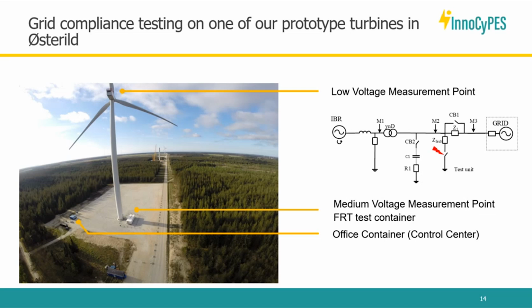We can obtain different topologies of faults by changing these impedances. You can apply two-phase or three-phase faults, and basically, from the point of view of the turbine, it's a fault that the turbine should ride through. This is a very established way of applying faults and validating and certifying turbines for faults, and this is what I'll show in the next slide or two.